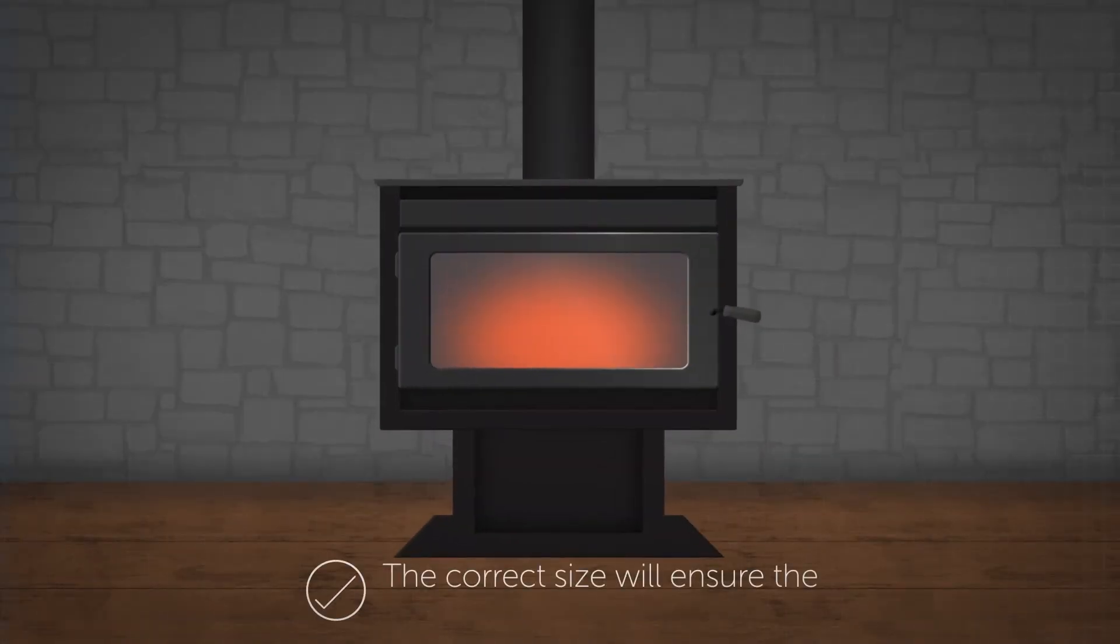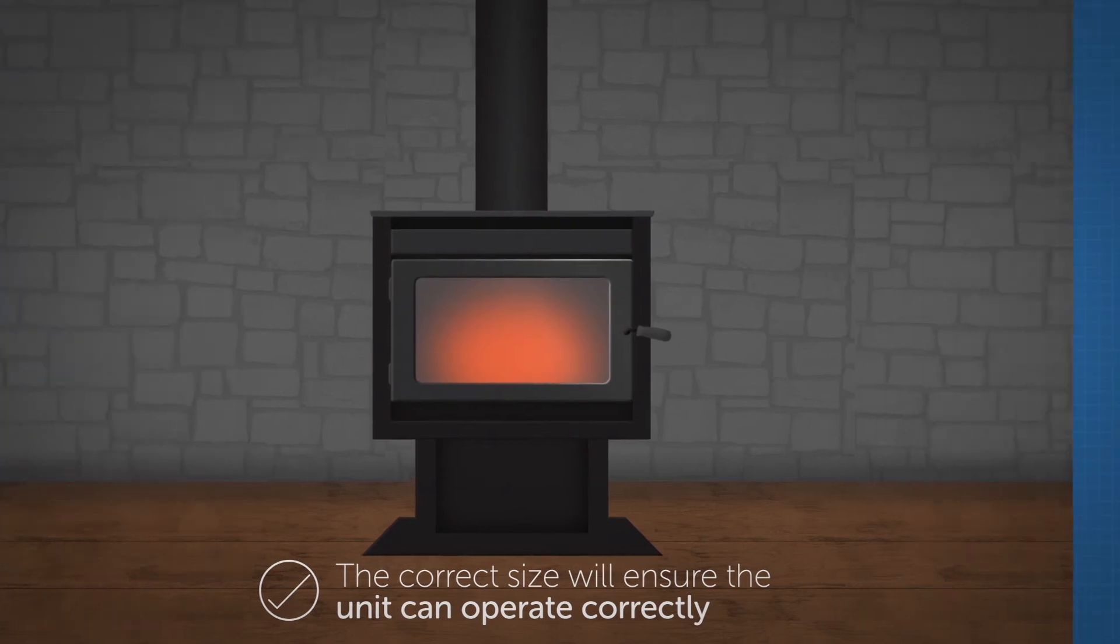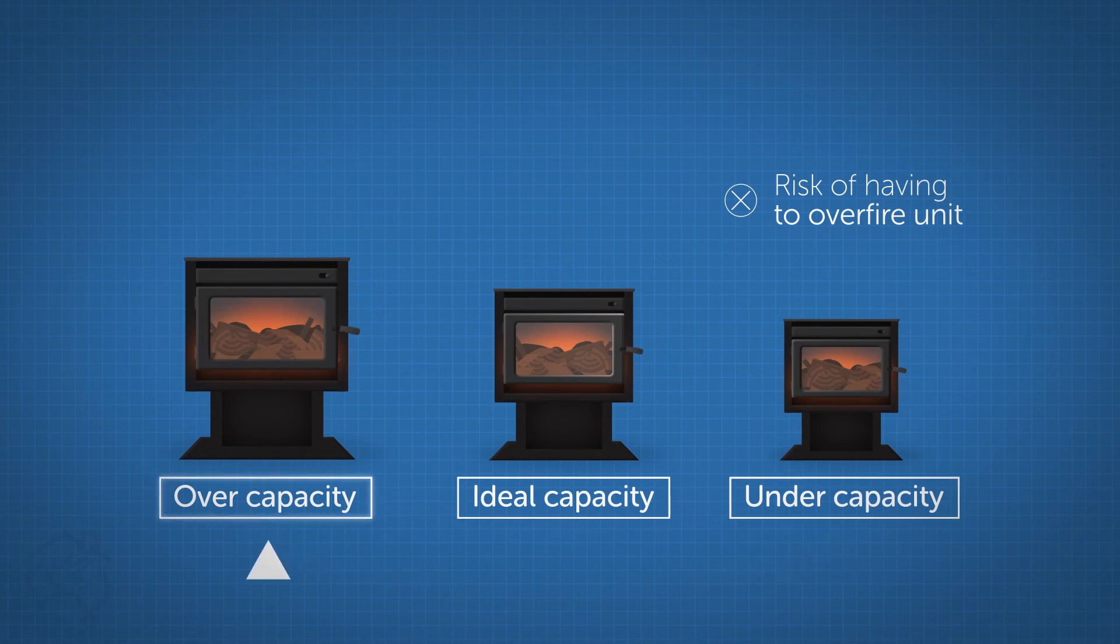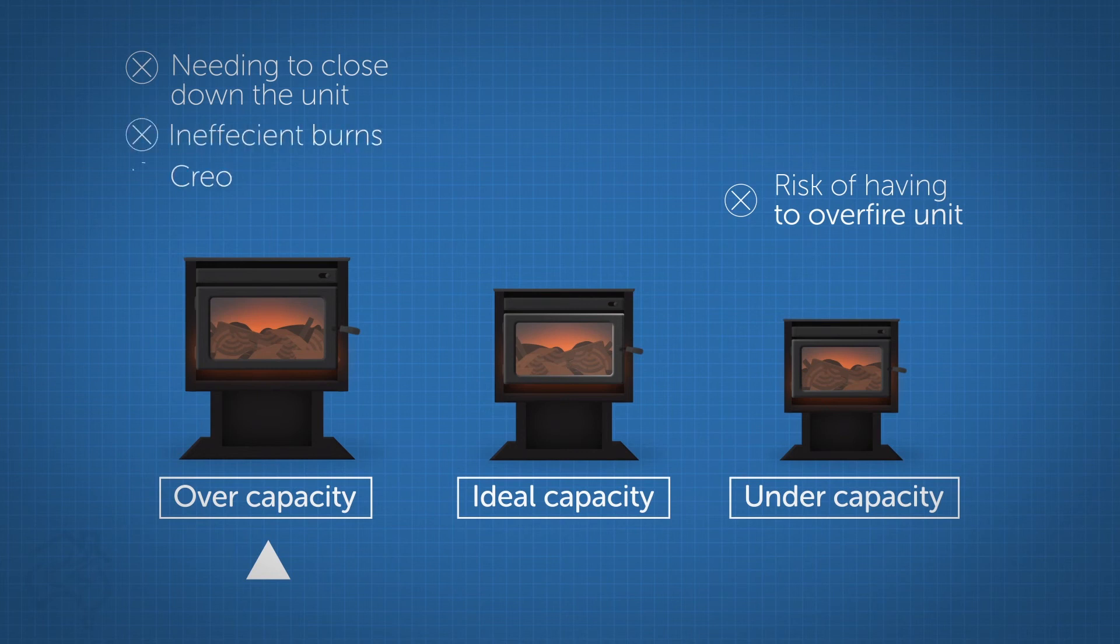Having the correct size unit in your house will ensure the unit can operate correctly. An undercapacity unit means you'll run the risk of having to over-fire the wood heater to have enough heat. Oversizing can lead to the unit needing to be closed down all the time, creating inefficient burns, dangerous creosote build-up in the flue, and excess smoke.